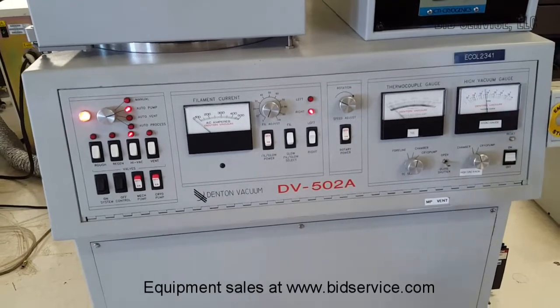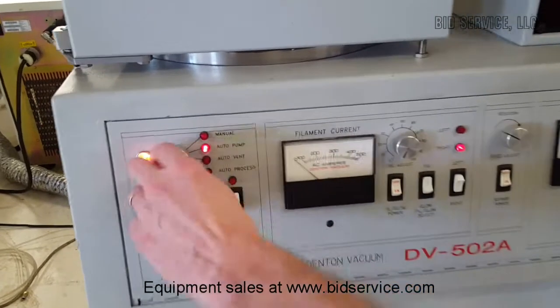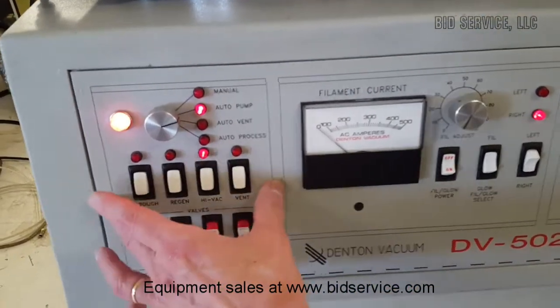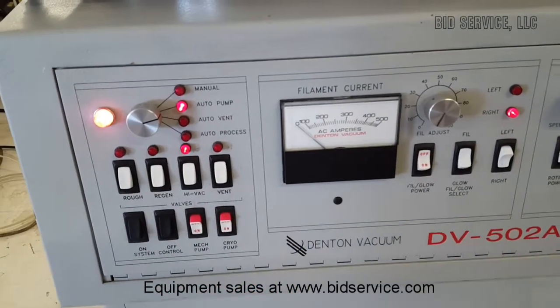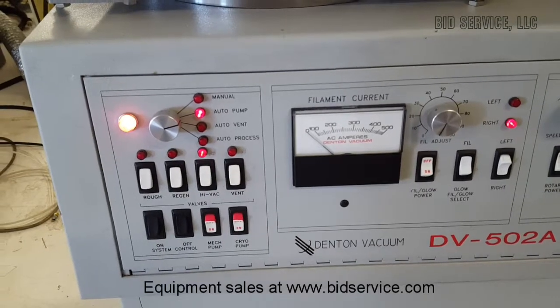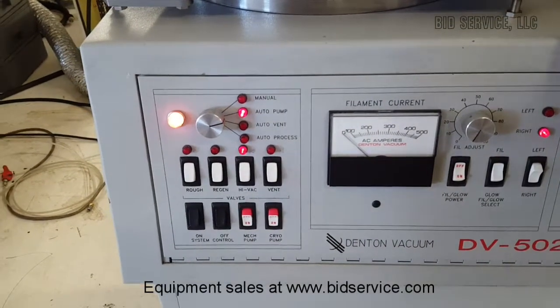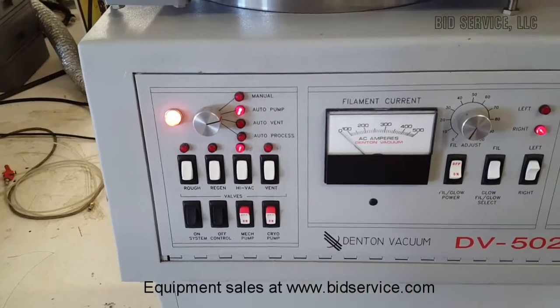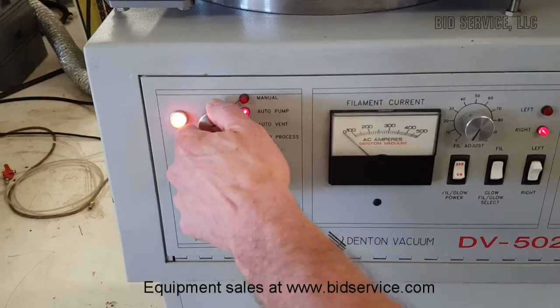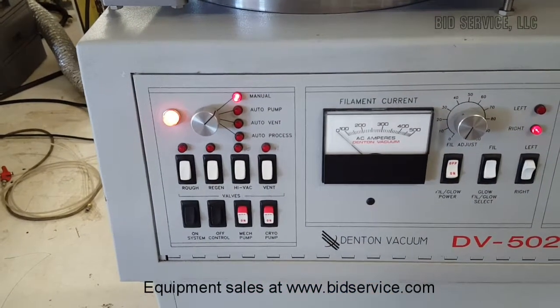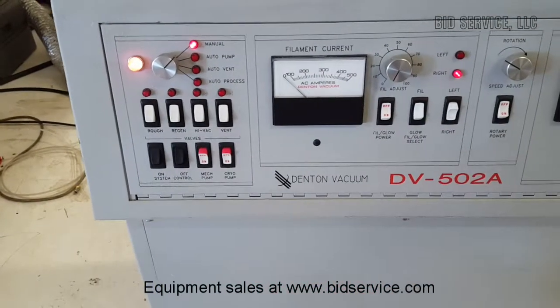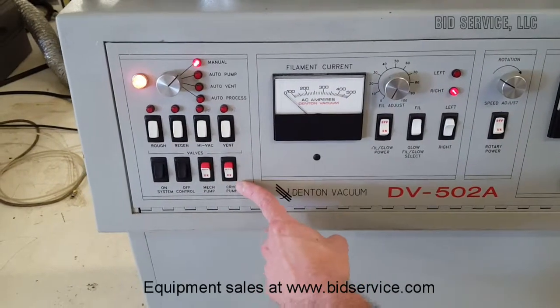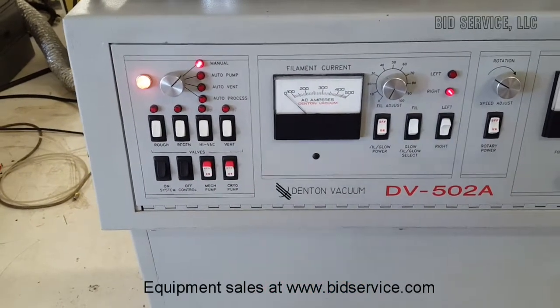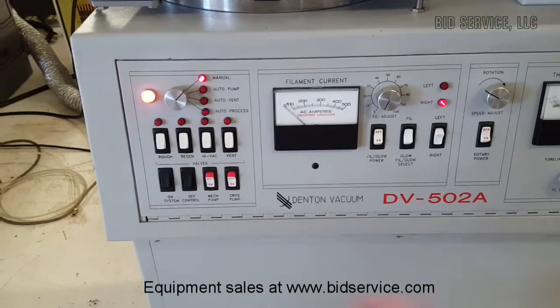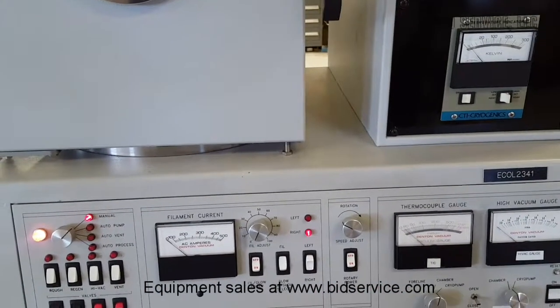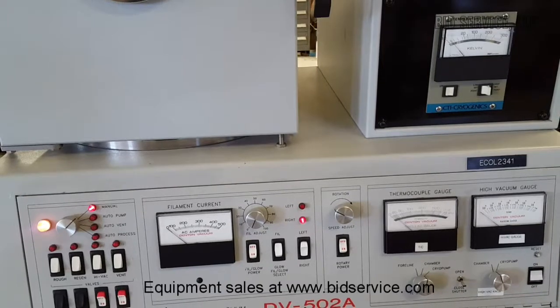Okay, I'll show you how to operate the machine. Again, we're under high vacuum now, so what I'm going to do is we can use auto vent mode. You do have a manual mode where you can control all these switches manually. You'll receive a manual on how to operate the machine, and you'll also receive a manual on the Inficon XTC/2, which is important for the automatic process mode. Anyway, we'll just switch this to manual for now. And what that does is it closes all these valves here. When you go to do a regeneration, you'll close it like this. You can shut your cryo pump off here, go underneath, open that valve, and vent the cryo with the nitrogen, and allow it to warm up, and you can monitor the temperature here. And you can go through a regeneration, which is explained in the manual.